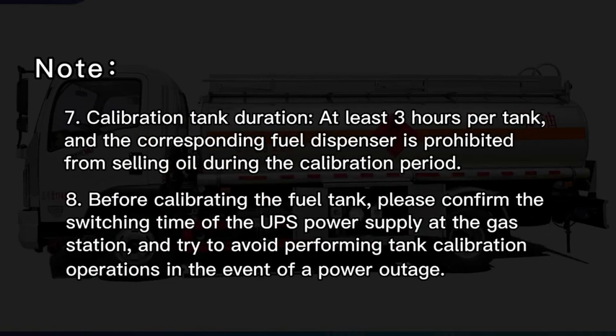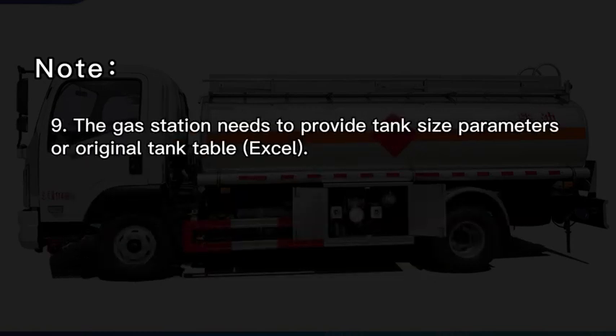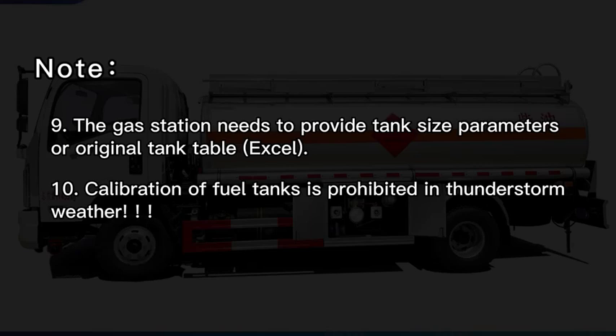7. Calibration duration is at least 3 hours per tank, and the corresponding fuel dispenser is prohibited from selling oil during the calibration period. 8. Before calibrating the fuel tank, please confirm the switching time of the gas station's power supply and try to avoid performing tank calibration operations in the event of a power outage. 9. The gas station needs to provide tank size parameters or original tank table (Excel). 10. Calibration of fuel tanks is prohibited in thunderstorm weather.